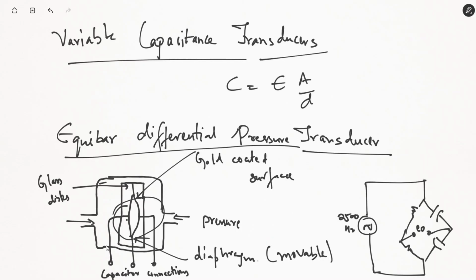It can be pressure because of air, it can be pressure because of any fluid that actually compresses the glass surface, that causes the diaphragm to compress. With compression, the distance between the diaphragms decreases, and that equivalent pressure can be transduced into measurement of capacitance.